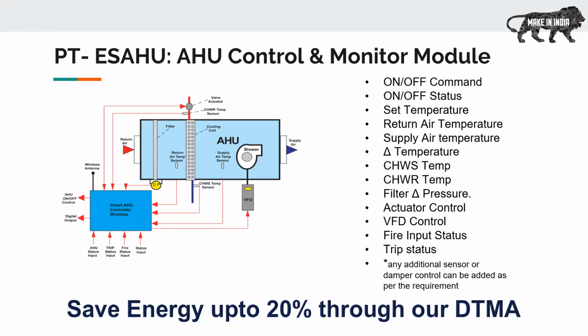Let me highlight the features of our standard basic module for HVAC chilled water based AHU, where we can give an on-off command, know the on-off status of the AHU, set the temperature, measure the return air temperature, and measure the supply air. This is to identify the performance of the cooling coil. If it is 8 degrees or above, it means the AHU is working efficiently. Then your delta T, the chilled water supply, chilled water return, then filter delta pressure to monitor the clogging of the filter. Based on these four temperature parameters, we control and modulate the actuator as well as take the feedback.